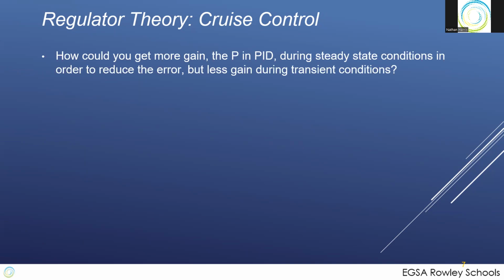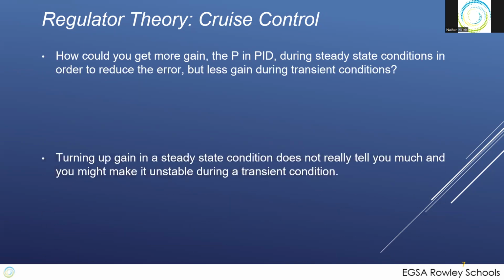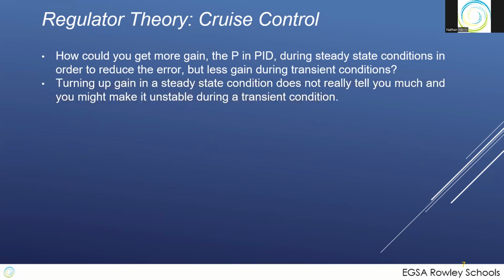So turning up the regulator in a steady state condition doesn't really tell you much. We actually used to hand out screwdrivers to people who were doing regulator tune-ups on drive systems. And here, tune them up, turn them up. The young engineers would go out and spin them up. Oh, the gain's going better. Look, it's going better. They would call it job security, because sure enough, we'd come back later and have to retune it, because they would tune it up too high, and it would make it unstable during the transient condition. So transient conditions are when you really should be tuning, measuring, not steady state conditions.